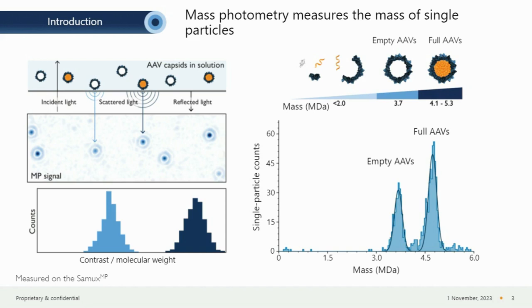The contrast generated by each individual single particle — how dark the center becomes versus lighter surroundings — depends on scattering capabilities. The more scattering we see, the bigger and more optically dense the particle is. Both parameters directly correlate with molecular weight. By analyzing the contrast and performing molecular weight calibration, we can directly determine the molecular weight of respective particles. The outcome of a mass photometer is a mass histogram, with counts on the y-axis and contrast on the x-axis, which converts to molecular weight of single particles in solution.